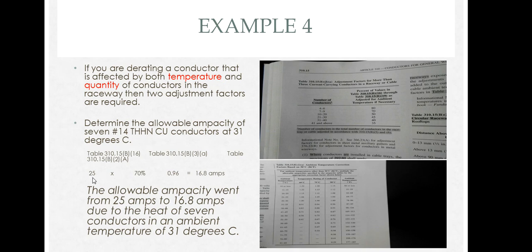We simply multiply 25, which is our starting ampacity of a number 14 THHN, by 0.7 and by 0.96, and we get an ending derated ampacity of 16.8 amps. That's the allowable ampacity for those seven conductors in the raceway. We went from 25 amps to 16.8 amps due to the amount of conductors in the raceway and the temperature of the ambient environment.